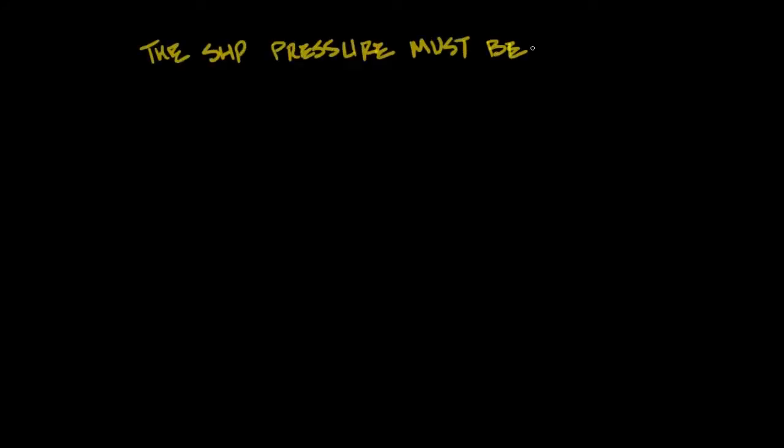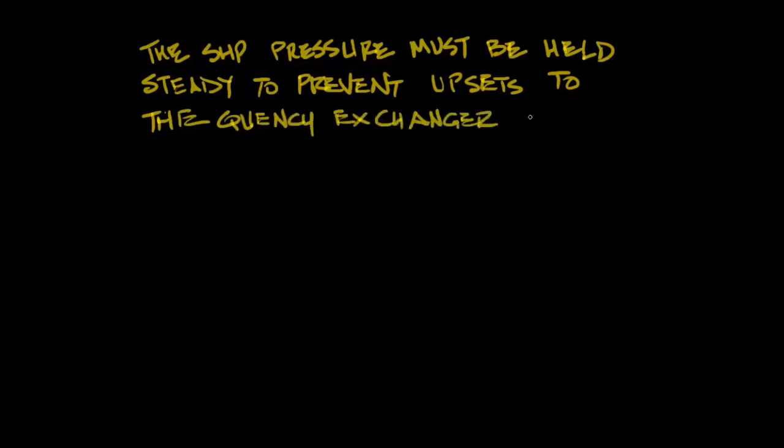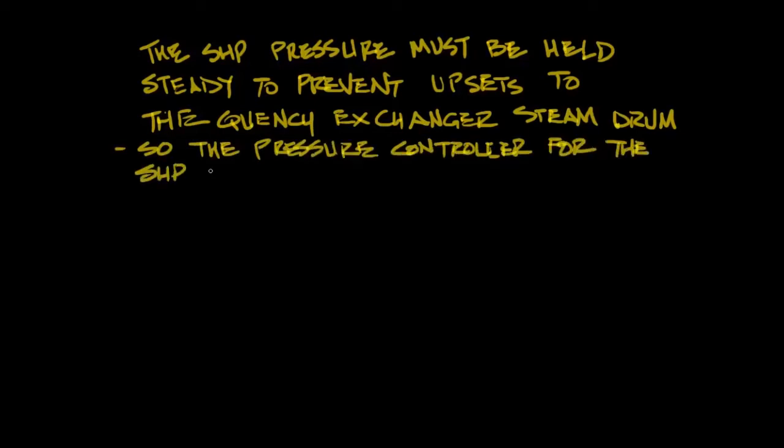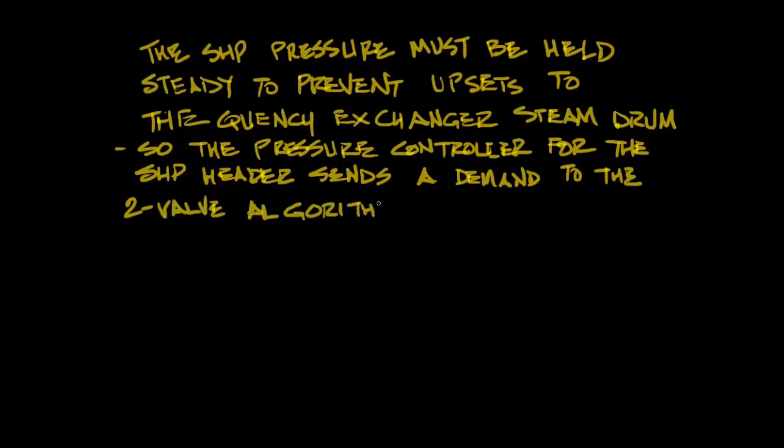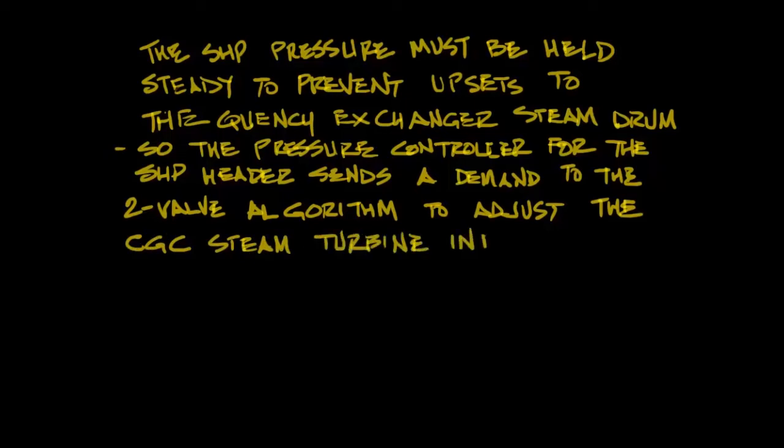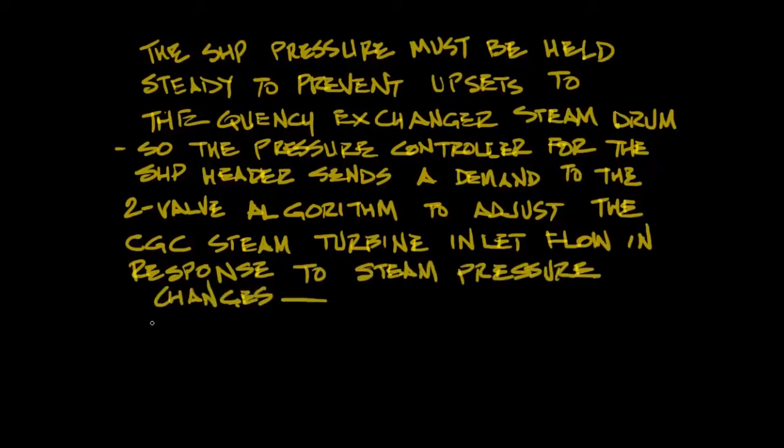The super high pressure steam pressure must be held steady in order to prevent upsets to the quench exchanger steam drum. You don't want high levels, low levels, so you have to manage that by keeping that pressure constant. The pressure controller for the SHP header will send a demand to the two valve algorithm to adjust the flow of the crack gas compressor steam turbine inlet in response to a steam header pressure change.